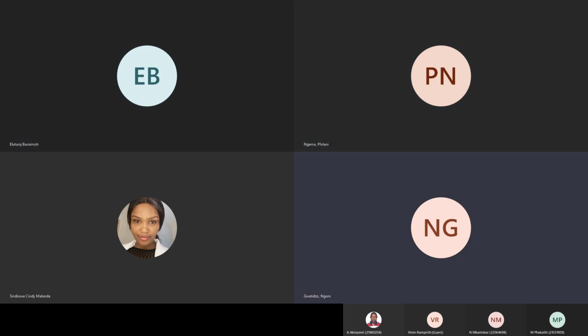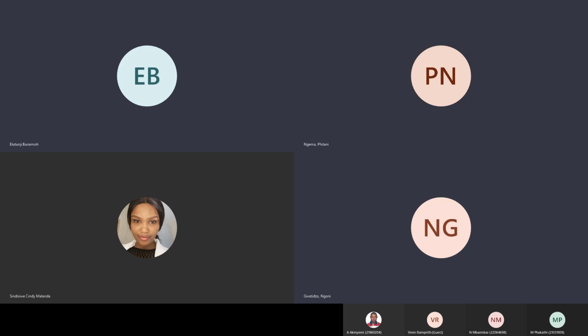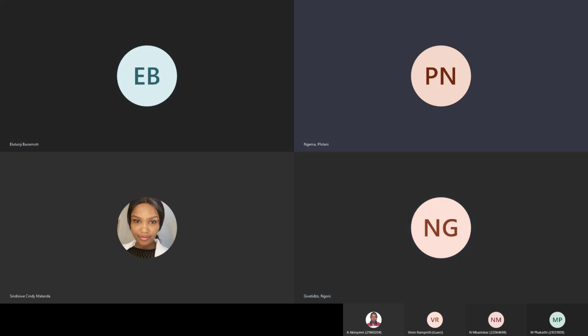Sorry, Mr. Philani. At the moment, what kind of furnaces are you talking about? What are they? And what size of transformers are they operating on? It's 100 MVA. The furnaces are DC furnaces. They feed the thyristors, and the thyristors are rectifying the AC to DC toward the furnaces. However, the thyristors cause a lot of harmonics back to the system, so we also have the power factor correction system to ensure that the harmonics are not affecting the transformer that much.